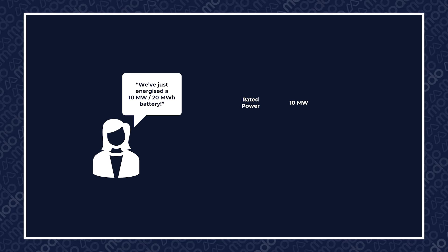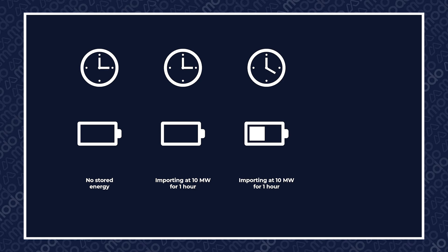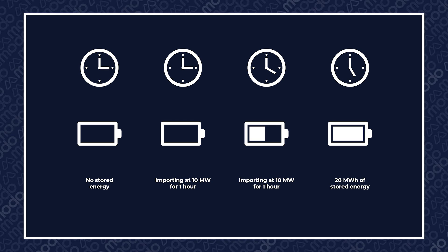Let's break this down. 10 megawatts just refers to the rated power of the site — that is, the highest rate at which the battery can import or export electrical energy. 20 megawatt hours refers to the amount of energy the battery can store. So in this example, if the battery has no stored energy, it could import at 10 megawatts for two hours to store 20 megawatt hours of energy. In this example, we'd say the battery has a two hour duration, but that's a story for another day.